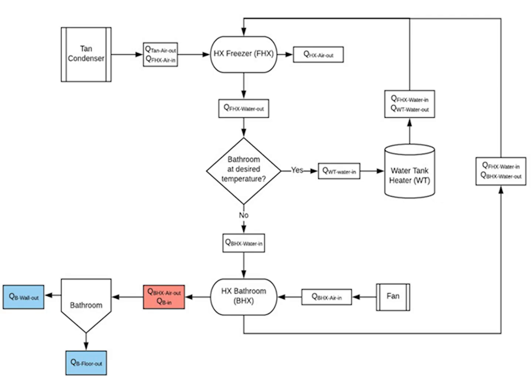To warm the restroom, energy from the hot air exhausted from the condenser is transferred to water flowing through a cross-flow heat exchanger. A fan located above the restroom moves air through a second heat exchanger. Energy is transferred from the warmed water to the air, and then the air is diffused into the restroom to increase its temperature. This cools the water, and the cycle continues.